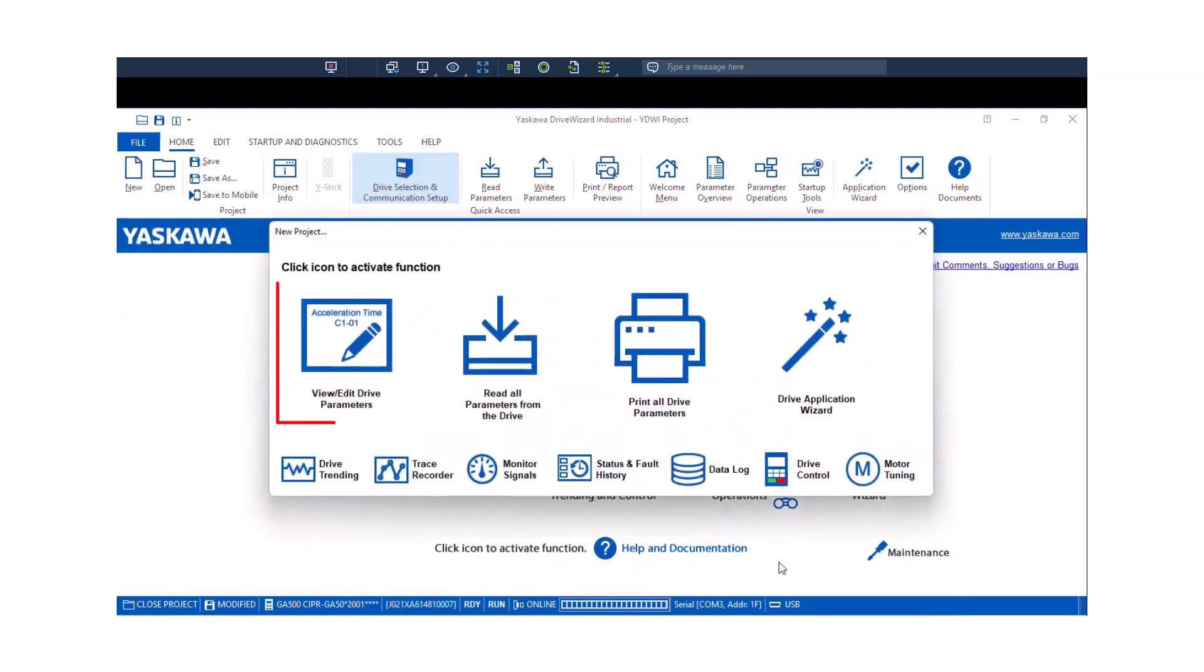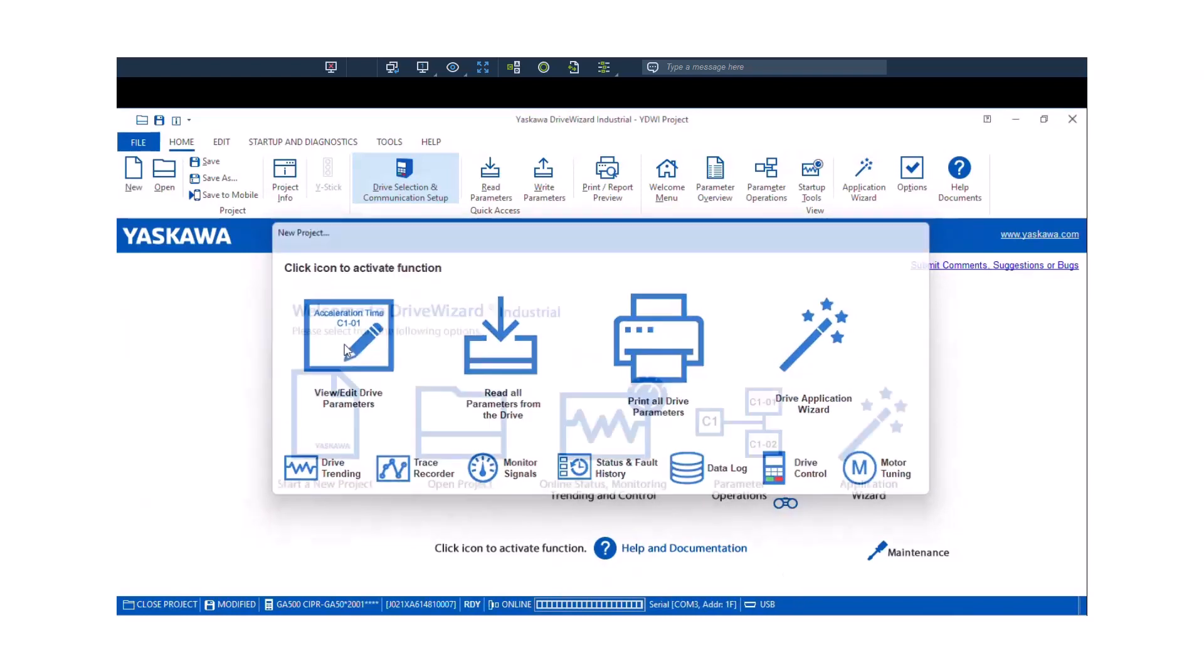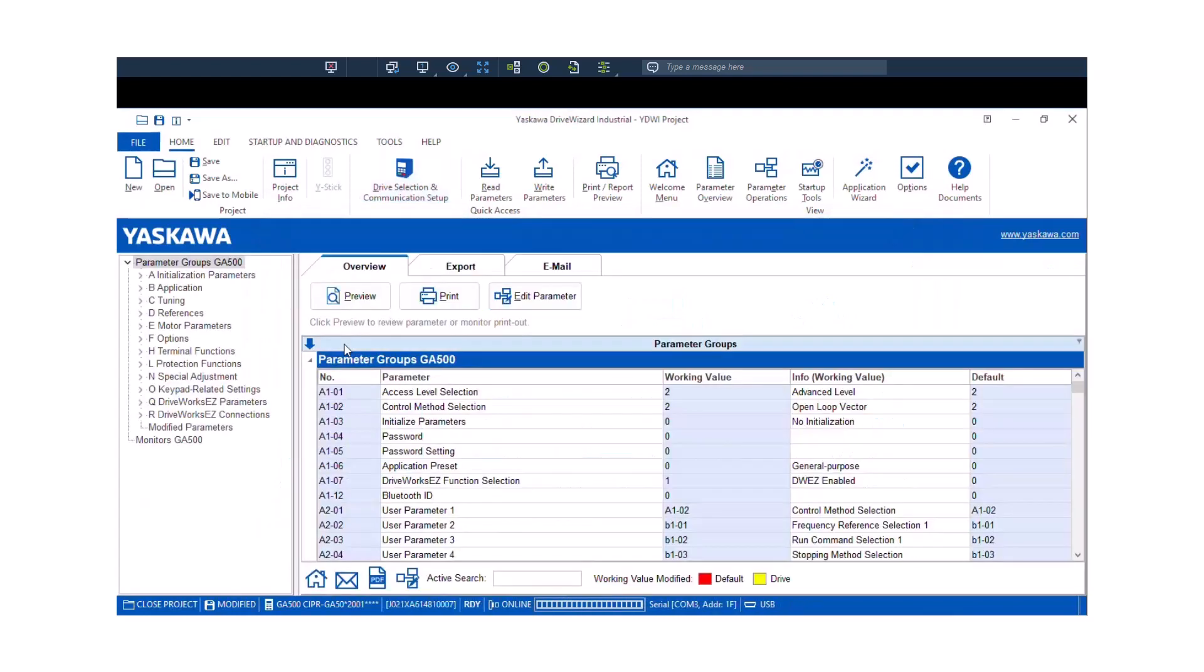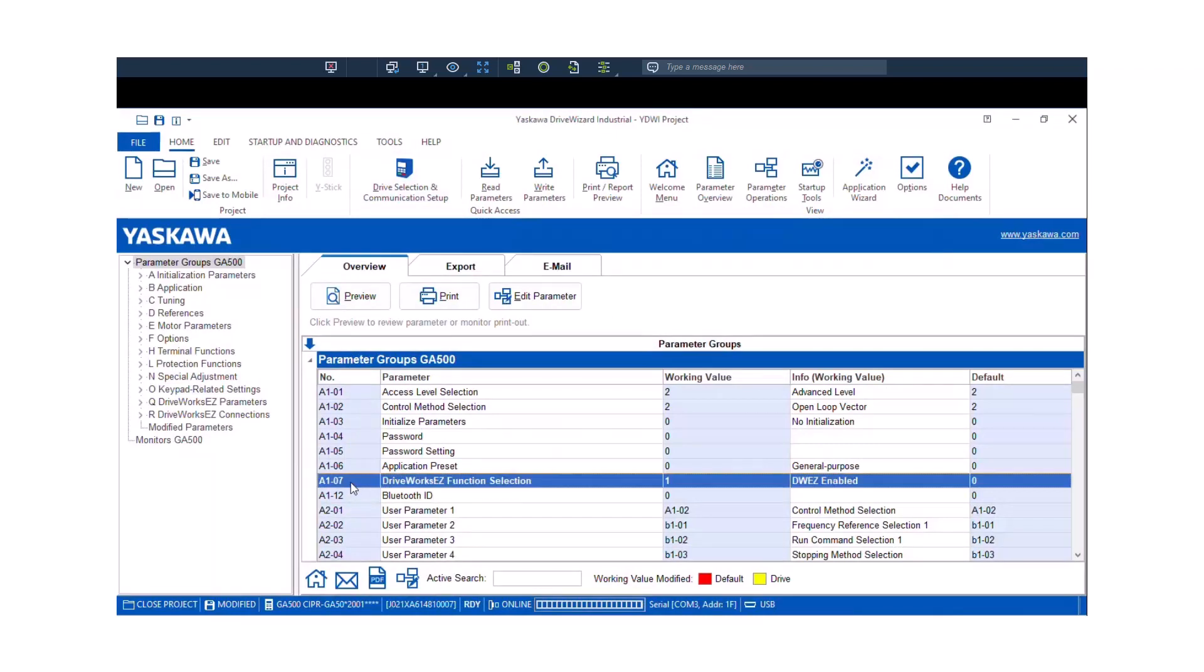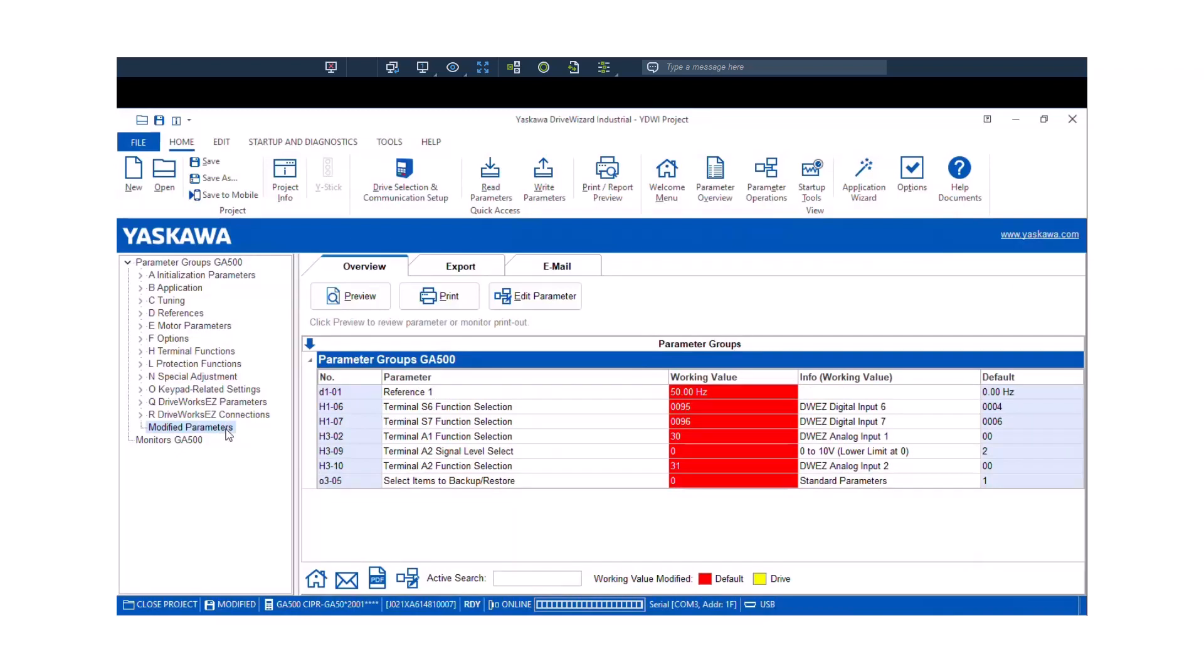I'm just going to view the parameters so I can see that the DriveWizard Z function selection, parameter A1-07, is enabled. So DriveWorksEZ is already enabled on this drive. Anything in red is a modified parameter. So we can just click on the left, modified parameters, and you can see all the parameters that have been changed. So it looks like there's some DriveWorksEZ programming set up already in this drive. You can see that the digital inputs and digital output and analog input are allocated for these DriveWorksEZ functions.